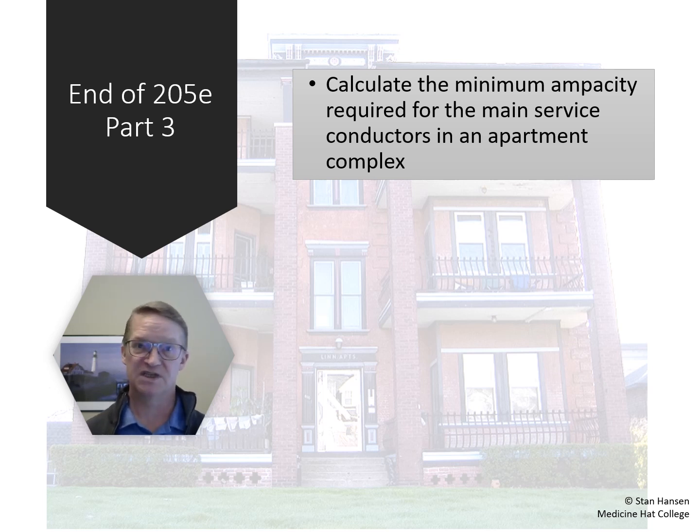We start with our suites minus the heating, EV, and car heater loads. We add it all together as per 8200 Subrule 3. After we have all that in, we put all of our heating loads together in one lump sum and then apply Section 62 to that load. For all of our EV and our car heating receptacles, they all go in at 100%, and our remaining loads not found inside the suites all get added to the service at 75%. Once you have your total loads, you divide it by your voltage to get your amperage, and then use Table 2 and Table 13 accordingly.